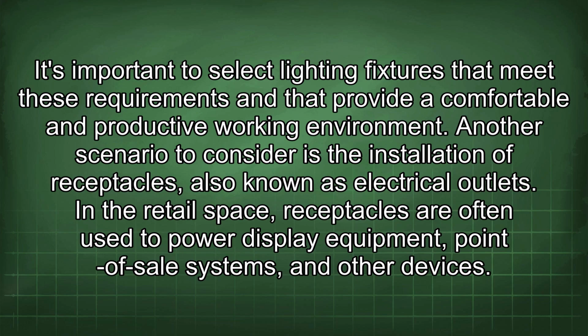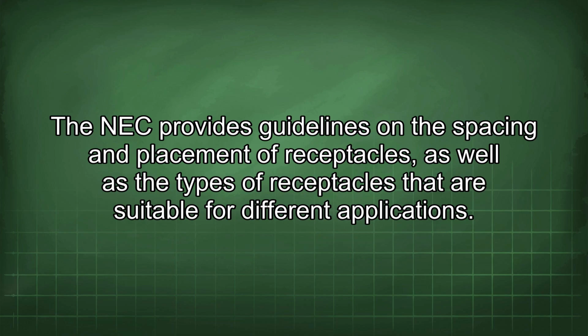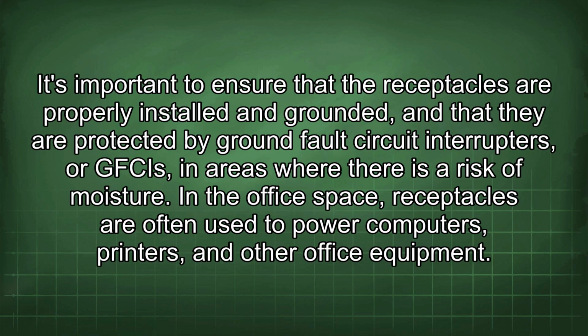Another scenario to consider is the installation of receptacles, also known as electrical outlets. In the retail space, receptacles are often used to power display equipment, point-of-sale systems, and other devices. The NEC provides guidelines on the spacing and placement of receptacles, as well as the types of receptacles that are suitable for different applications. It's important to ensure that the receptacles are properly installed and grounded, and that they are protected by ground fault circuit interrupters, or GFCIs, in areas where there is a risk of moisture.